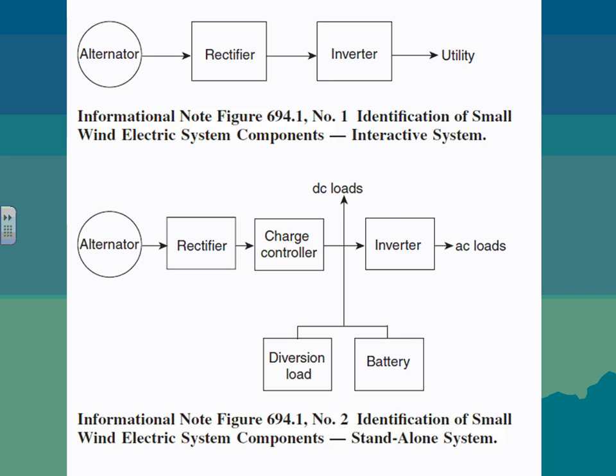So that's very, very important with a small system, because typically the speed of the wind is a non-controllable item, right? From a design point of view. And there are a lot of ways, guys, to deal with the speed of the wind in order to control the frequency of the alternator. And if you're in the electrical field, engineers and electricians, you fully understand what I'm talking about, the frequency over here.